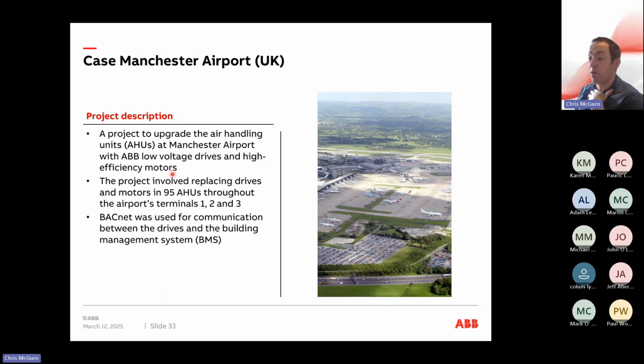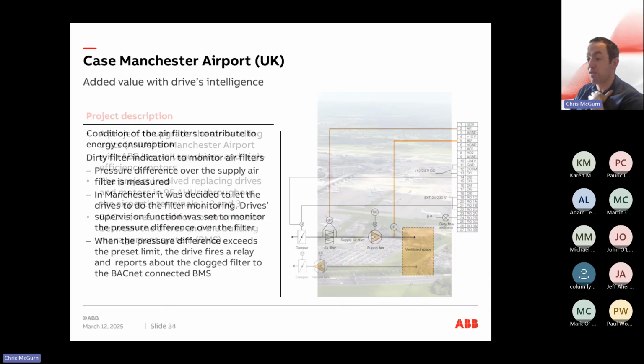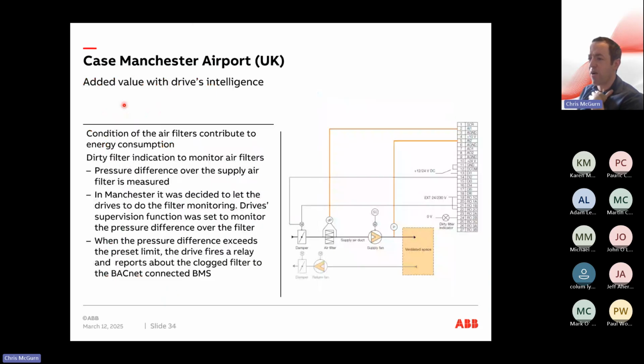And yeah, they were replacing 95 different air handling units throughout their terminals, and they use BACnet to communicate with their building management system. So the condition of their air filters contributed to their energy consumption. They were seeing a lot of dirty air filters, and that was blocking up the systems and causing pressure differences and causing increased load that was unnecessary.